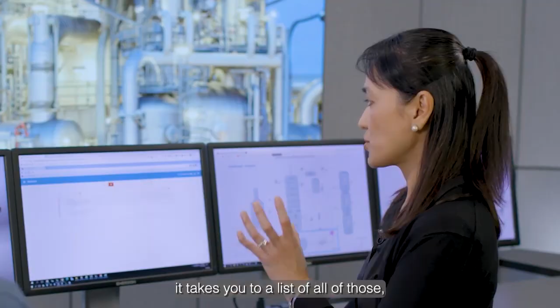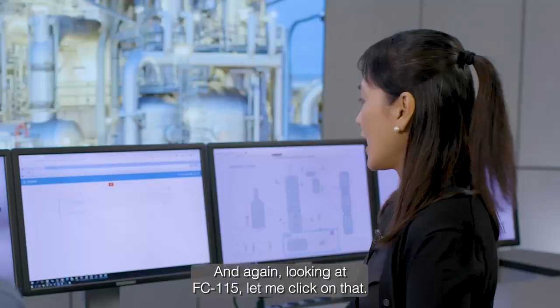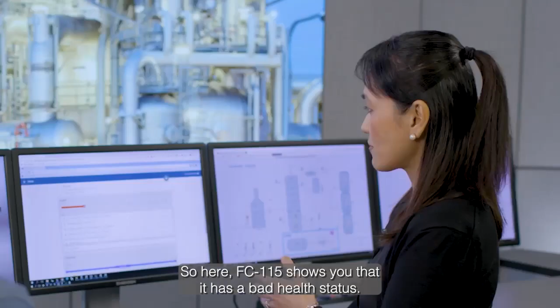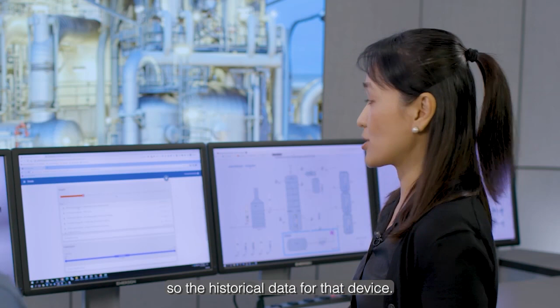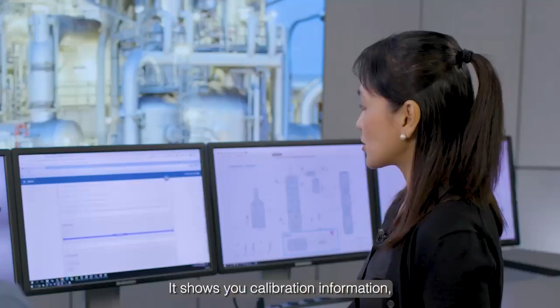I click on the bad ones, and it takes me to a list. Right now we have 2 devices needing attention. Looking at FC115 again, let me click on that—it provides a more detailed view of what's happening on that device. It shows that FC115 has a bad health status, and even gives the past 20 alerts, so the historical data for that device. It shows calibration information and even when the configuration was changed on that device.